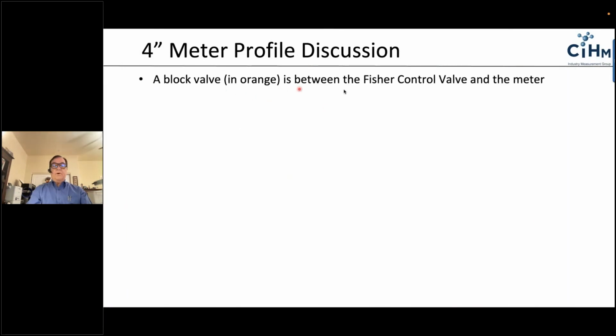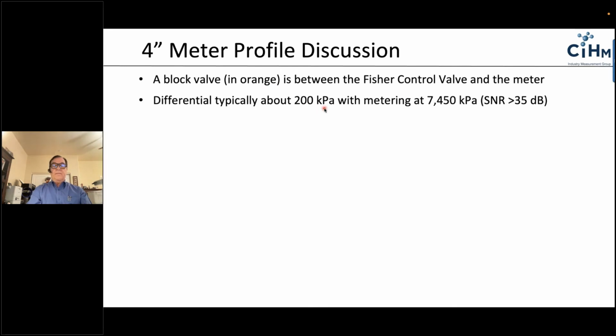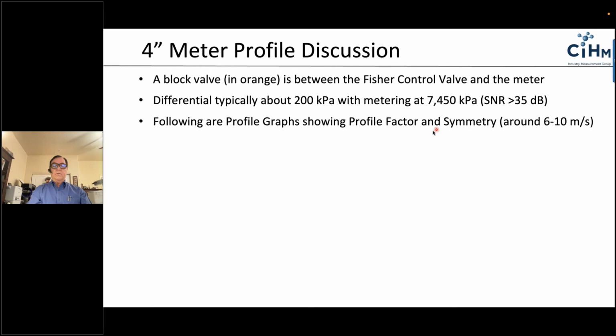So the block valve in orange, again, is between the Fisher ET and the meter, typically 200 kPa, with the metering pressure around 7,450 kPa. For those that are familiar with ultrasonic meters, the signal to noise is well in the strong range, 35 dB. If we get down around 15 to 20, like a lot of meters, that's where the meter might start rejecting waveforms. But the meter signal to noise is well in the solid range, no problem at all.